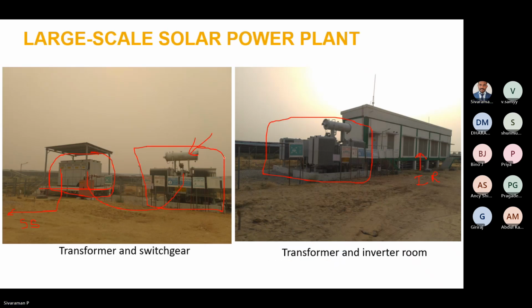There is one more thing called fencing. All the transformers will be protected by means of fencing. In order to avoid unauthorized entry or unauthorized accessibility, normally these transformers will be covered by a fence and it will be locked, so only the authorized person is allowed to access that. Also you can see there is a distance between this inverter duty transformer and the switchgear. This distance is called clearance between the transformers.